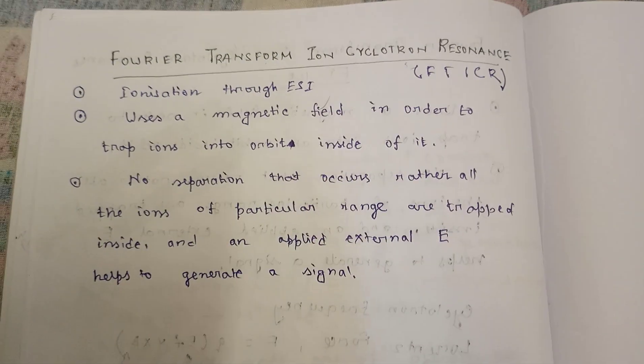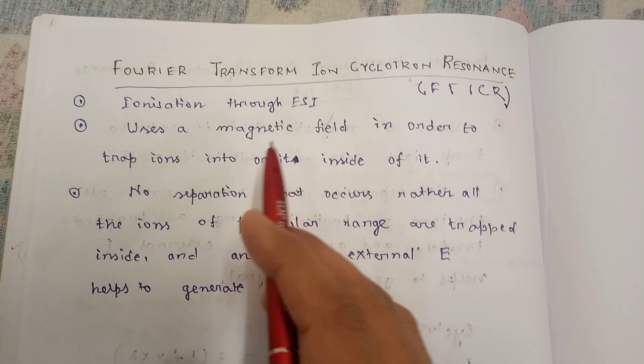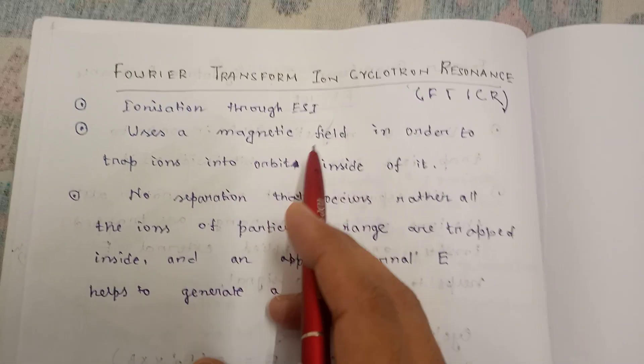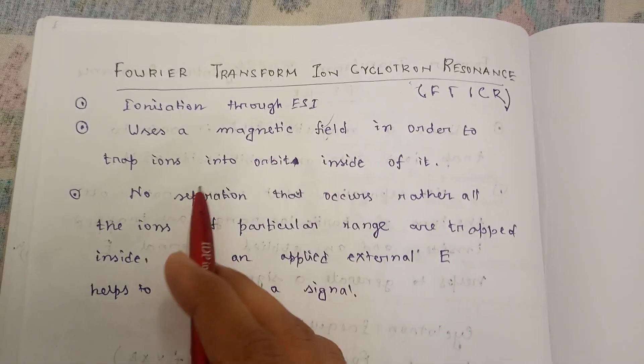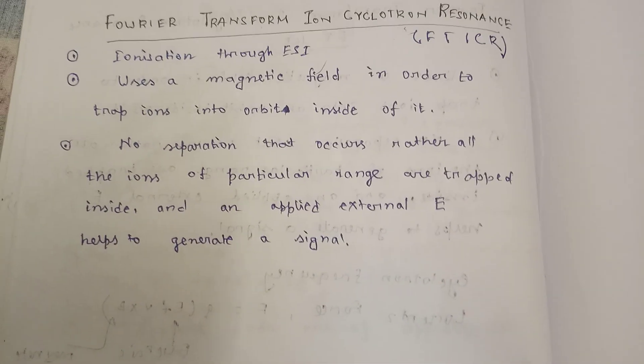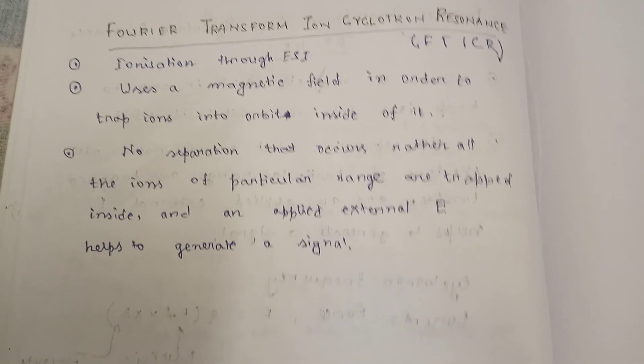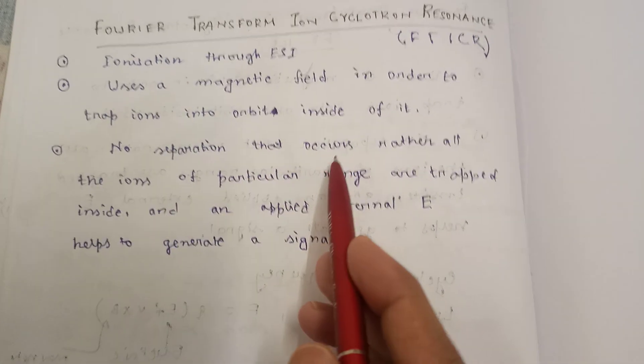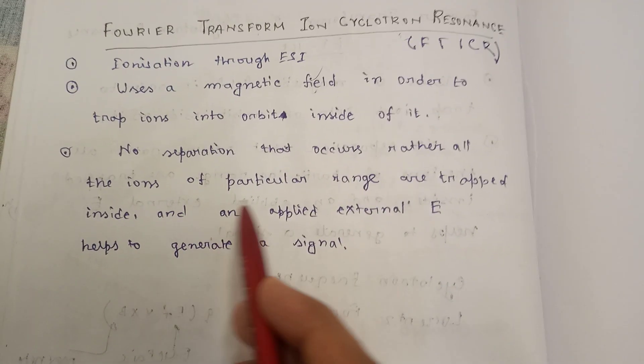After ionization, what happens? The magnetic field is used to trap ions into orbit inside of it. No separation occurs; rather, all the ions of a particular range are trapped inside.